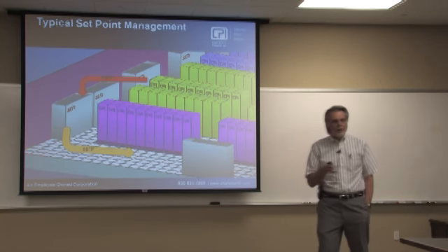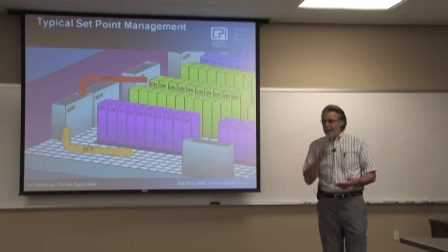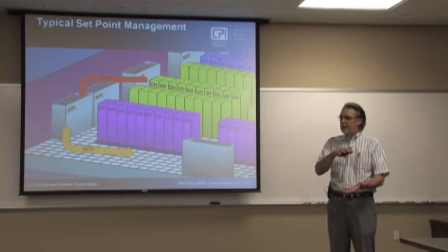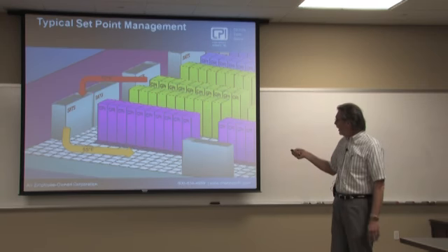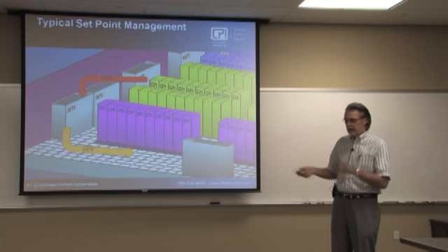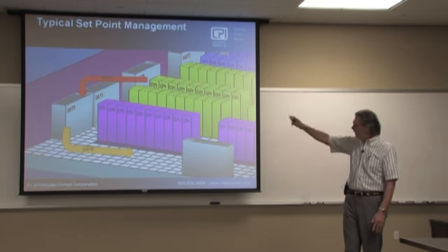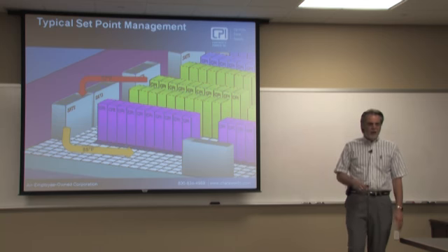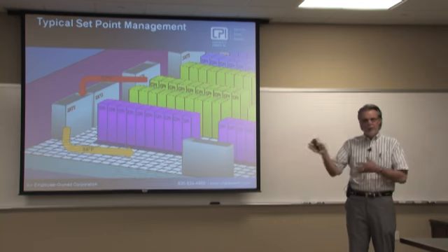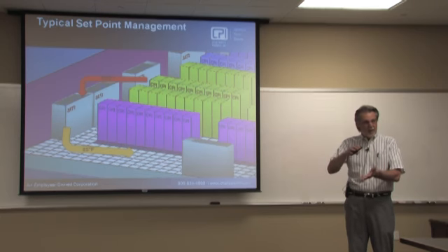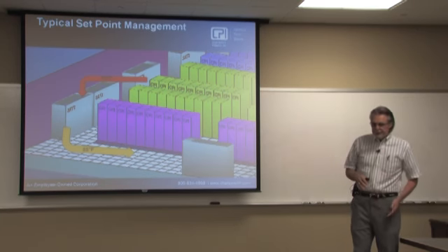Most computer room air handlers are rated at their cooling capacity based on an 18-degree temperature drop. So if we're setting 72, that should actually be 54 degrees on the supply. But you're typically going to see this kind of relationship, 72 to 55, 72 to 54, that kind of difference.